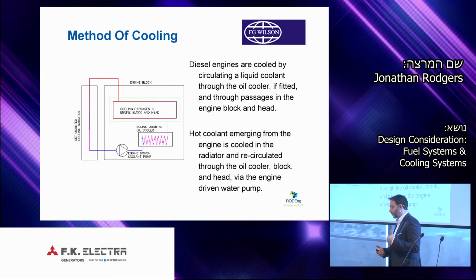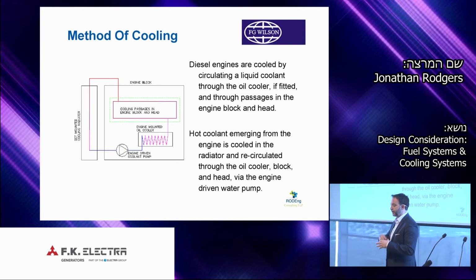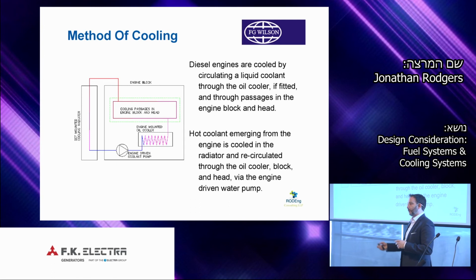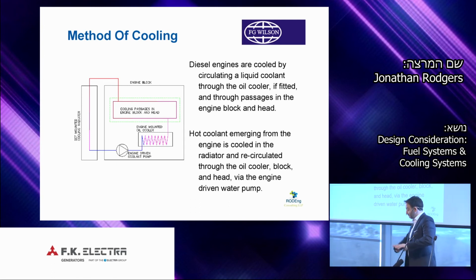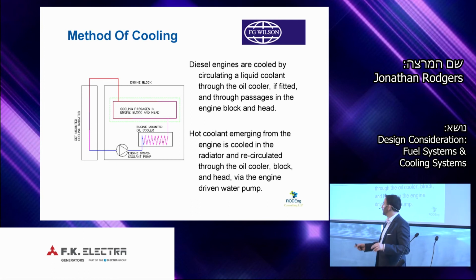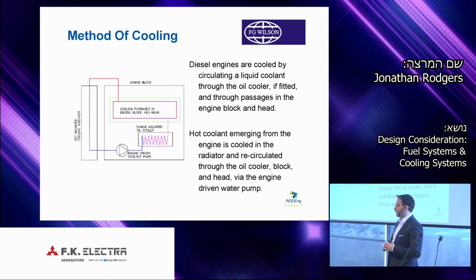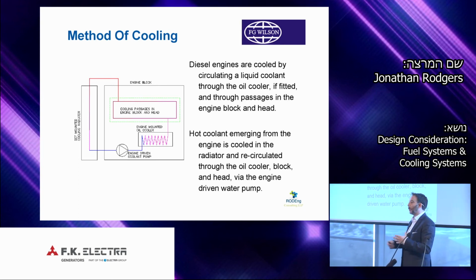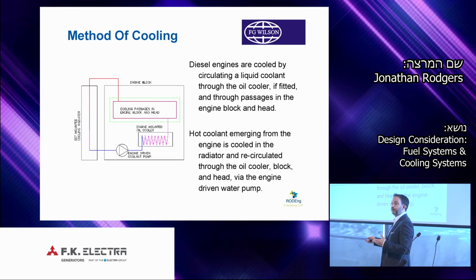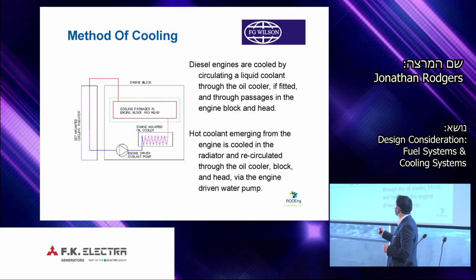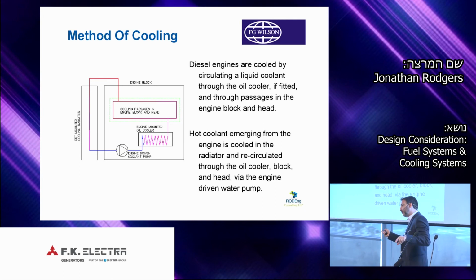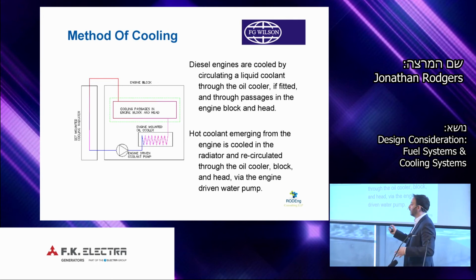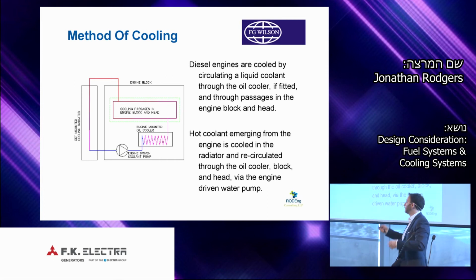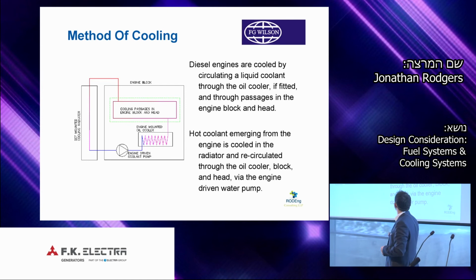So looking at engine cooling, and we think of the water circuit within the engine, the important point on energy balance, and this is in all brands of engine, is that we need to consider the jacket water, but also the oil. The oil is cooled through the cooling circuit and oil temperature maintained through that cooling circuit. And the engine pump will pump coolant through the oil cooler, through the passages of the engine block, and then back out to the radiator.